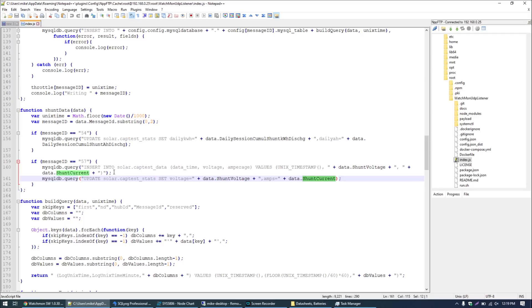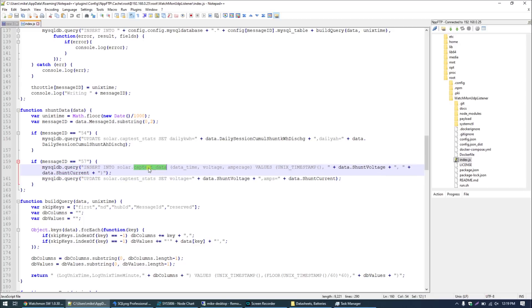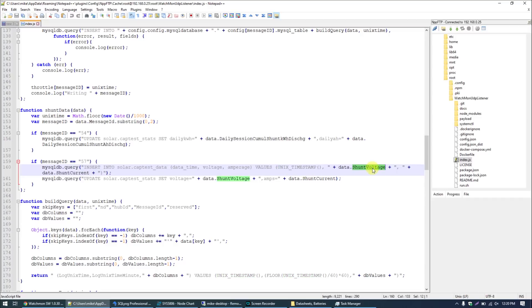On every occurrence where a 54 message ID is broadcast we update this table with the daily kilowatt hour value discharged and the daily amp hour value discharge. We're writing these two pieces of information every time they're broadcast from message 54. Additionally we're making some updates on message ID 57 to the same table cap test stats and we save the voltage and the shunt current. Additionally in the past two videos I've reviewed batteries, you'll notice I've presented line graphs of the discharge test. So I also have it every time a 57 is broadcast, we're logging that record to cap test data and that's an insert. It's not an update so we have a history of voltage and amperage tests throughout the capacity test of that battery.